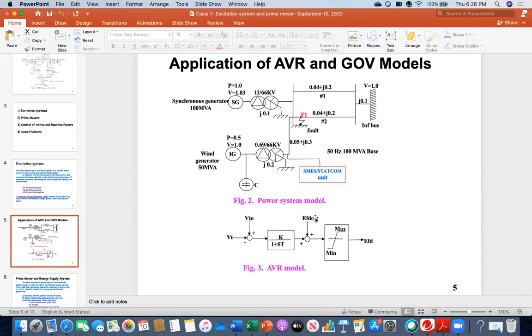So why is this needed? For example, suppose there is no difference in voltage. The system is running well, with no short circuit, no open circuit, nothing happened, meaning there is no difference. So the difference will be zero, and then the field voltage would ultimately be zero. But that should not be the case. That's why you see here that you always need some field voltage to excite the magnet, or the field circuit. This is a small value, but you need it.